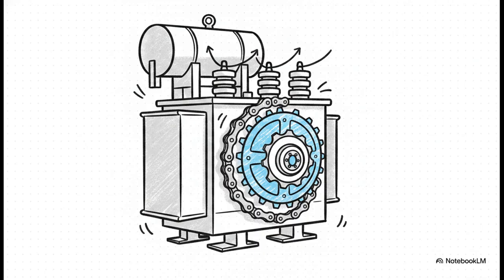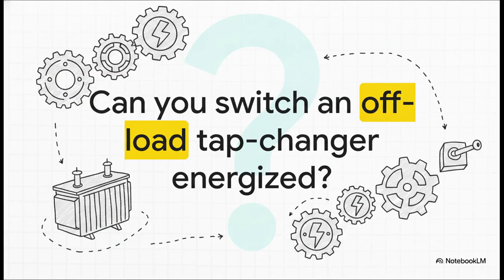Next up, we have the tap changer. And this brilliantly illustrates how we manage fluctuating voltages on the grid. Think of tap changers as, well, basically bicycle gears for voltage. They aren't changing how hard the transformer is working, they're just adjusting the turns ratio in discrete little steps to keep your output voltage exactly where it needs to be. Oil-immersed units usually give you about 7 adjustment steps, which is great for handling those wider voltage swings you see on long feeder lines. Dry-type units, on the other hand, are usually sitting much closer to the power source, so they typically only need about 5 steps. But dealing with these bicycle gears comes with a massive, massive caveat.